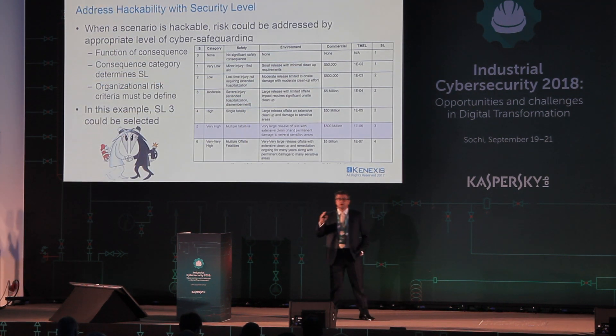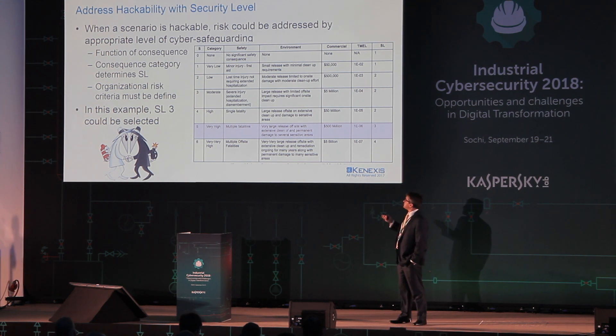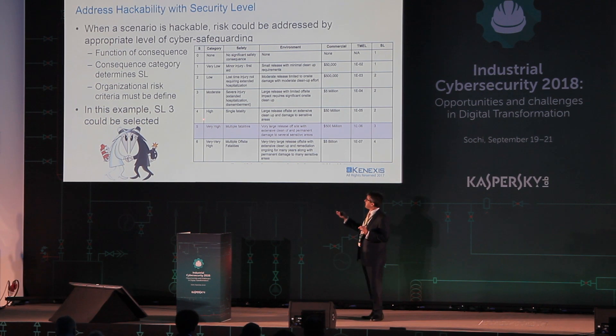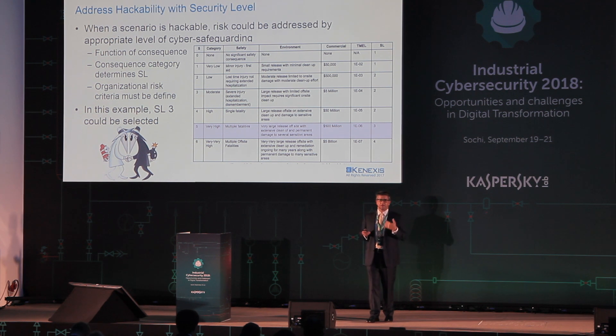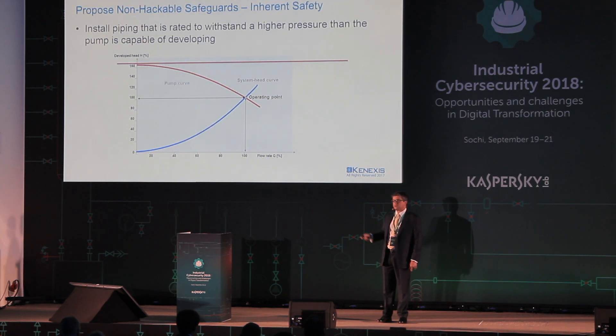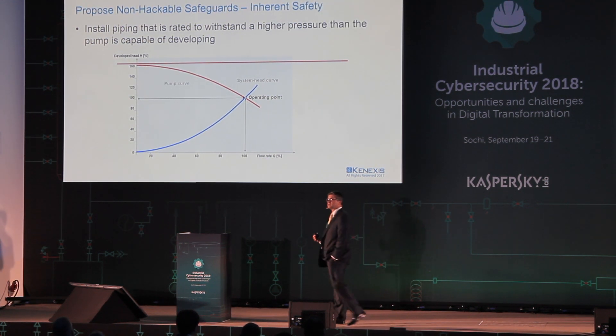We can use cybersecurity, and how much we need is a function of the consequence category. In this case, the consequence was multiple fatalities — high or very high. If that's the case, you need a very high security level to protect against that. The logic is: is it hackable? Yes or no. If it is, then what is the consequence? That defines your security level. In this case, we would pick security level three. But as a process engineer, I know that if I recommend SL 3, I've got the cybersecurity team trying to implement it. So what else can I do as a process engineer?